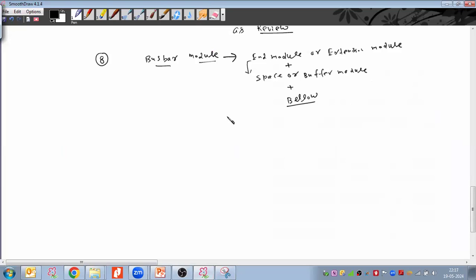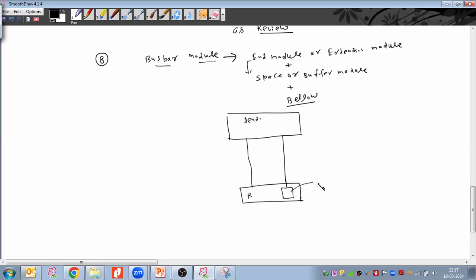let us take a substation here, and then the transmission line going to another substation. So this could be any sending substation, or it is a receiving substation. Now all the major equipment, the switching equipment, is placed in a metal enclosure and filled with SF6 gas. Now suppose that a fault happened in this transmission line, and we need to take this line under maintenance. So what do we do?